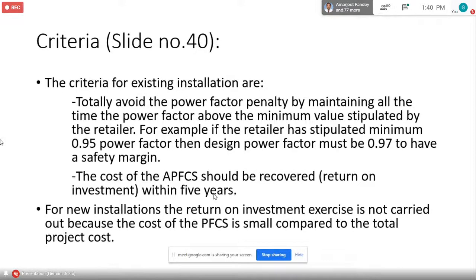Criteria. The criteria for an existing installation are to totally avoid the power factor penalty by maintaining, all the time, the power factor above the minimum value stipulated by the retailer. Common sense. For example, if the retailer has stipulated a minimum 0.95 power factor, then the design power factor must be 0.97 to have a safety margin. If you set it at 0.95, you could be in trouble. Okay, so set it higher.